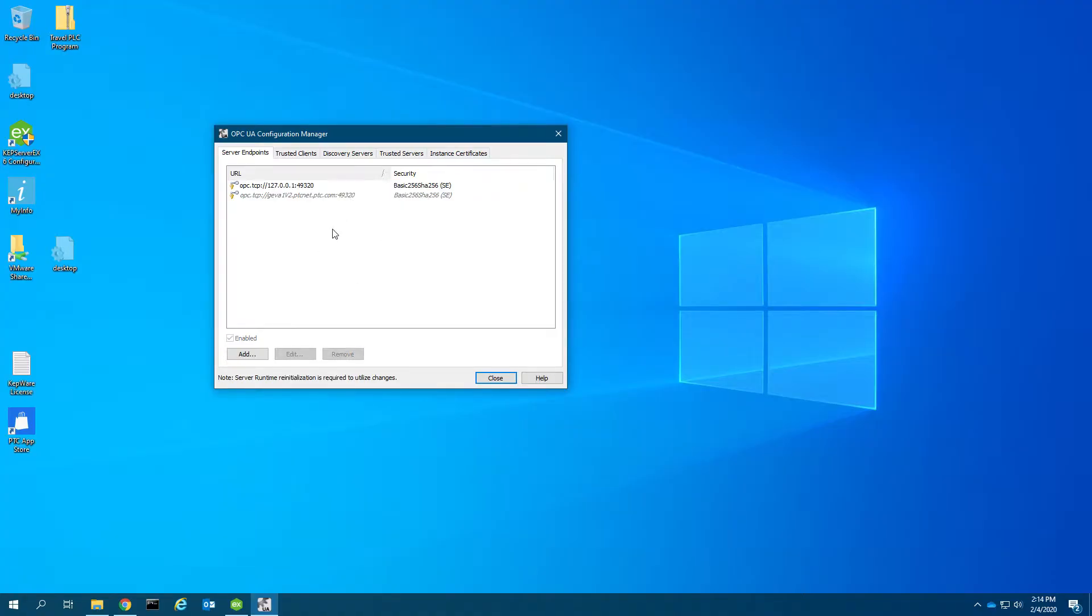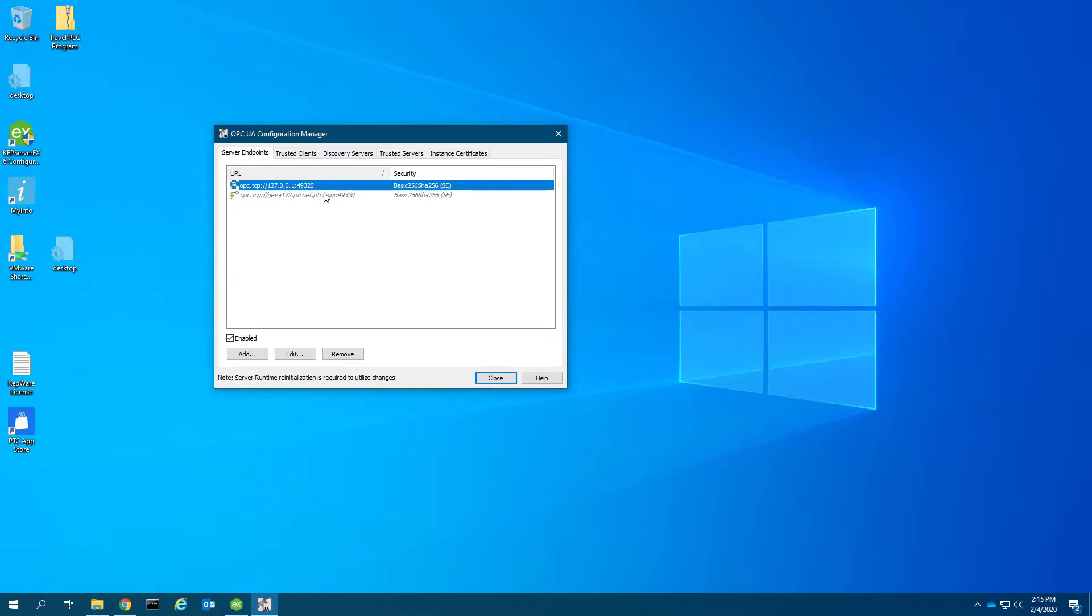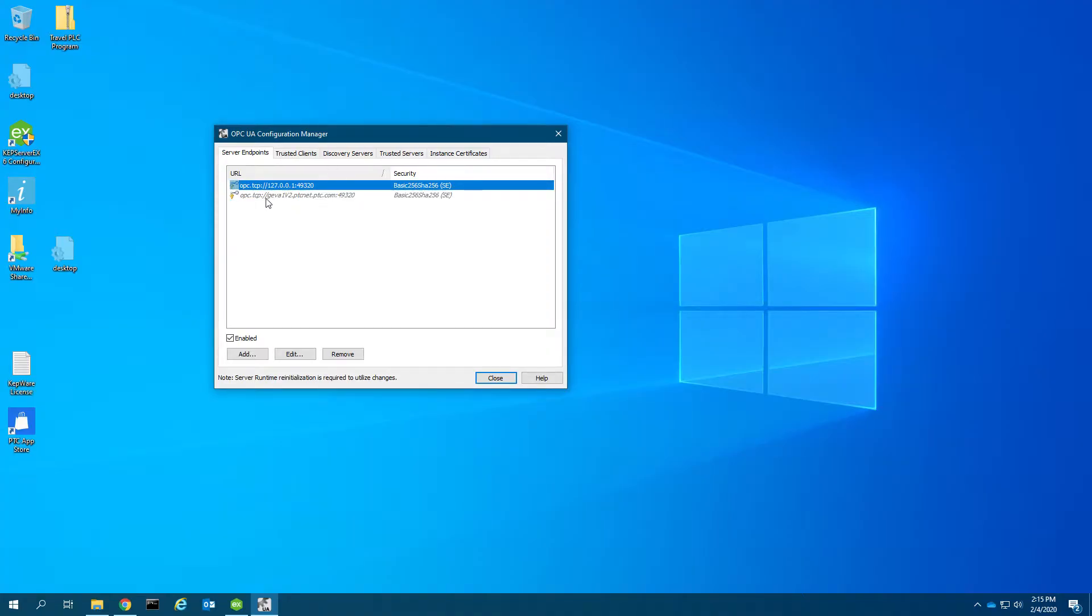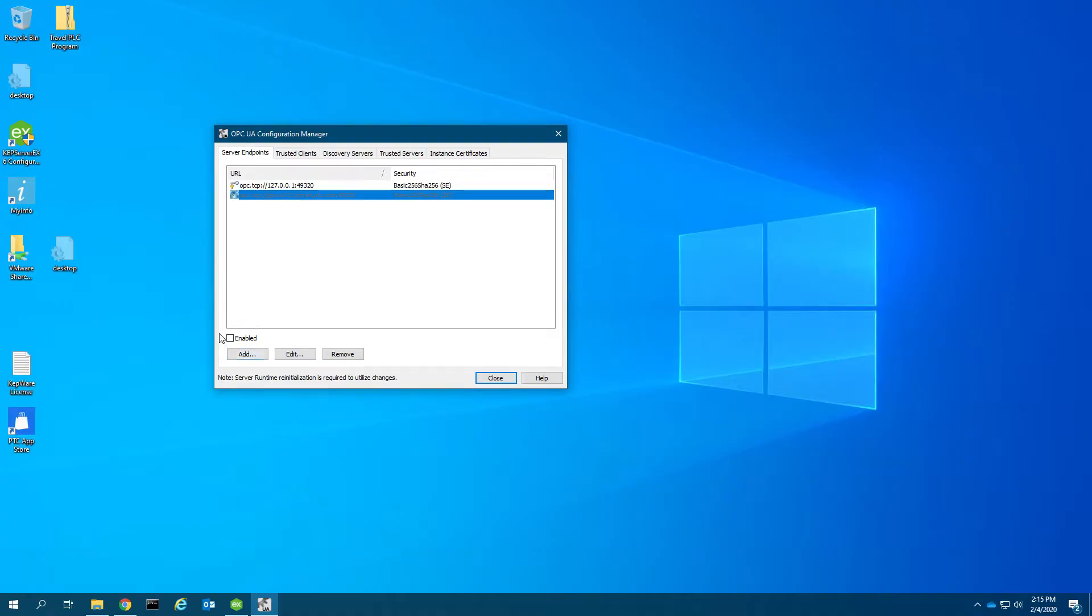OPC UA configuration is going to run as an administrator. I've got two endpoints set up by default. This first one, 127.0.0.1, is localhost, which enables the local OPC UA server interface. If I click on this one, which is the actual host name of my machine, I see it's disabled by default. I'm going to enable it so it binds the server to the actual IP of my computer.